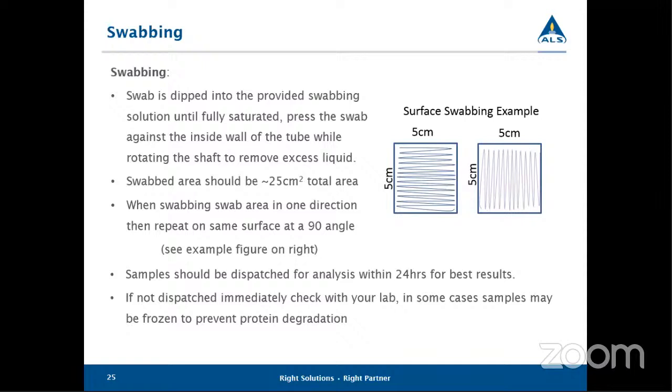So the swab itself, you'll dip into the solution and you'll want to remove the excess liquid. The swabbing area is fairly small. I have a couple examples there on the right of if you were to do just a small square. Obviously the shape that you swab does not need to be a square, just as long as it stays under that 25 square centimeters total area.